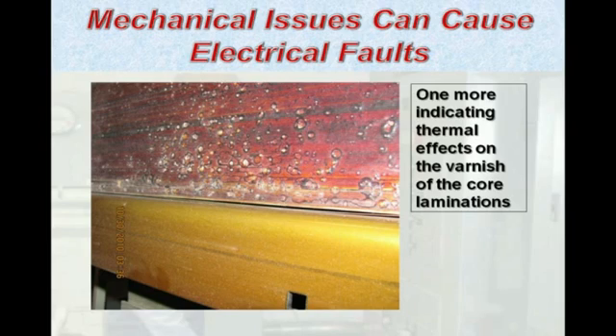All right, cool. Another one here, Joe. Do you know if the manufacturer in this case conducted a root cause analysis? I mean, did they figure out what the cause of this was? Was it poor manufacturing, poor workmanship, materials? What did they come up with? At the last time that I received information on this a couple of months ago, there were two theories. Number one, there was a manufacturing defect on the core laminates prior to dipping and baking, and the other hypothesis, which is still being investigated, is a misalignment upon joining the horizontal and the vertical core pieces with the miter joint. At this point, the primary suspect is a manufacturer defect.